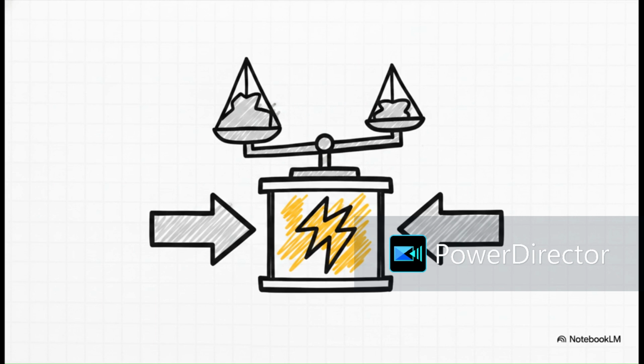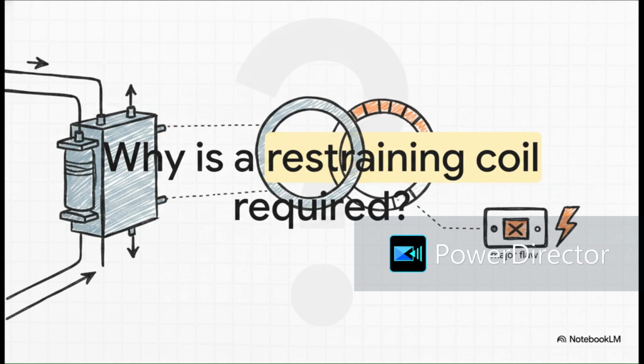If those numbers don't match up, it means current is leaking or shorting somewhere inside the transformer itself. Any unbalance inside that zone equals an immediate trip. But this introduces a pretty massive engineering problem, and it leads to a classic high-yield interview question to really test your understanding. So why is a restraining coil required in differential protection?